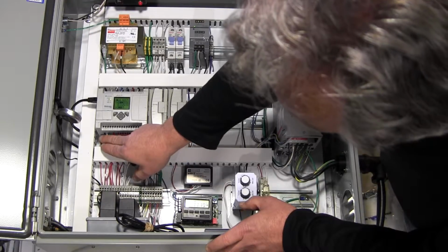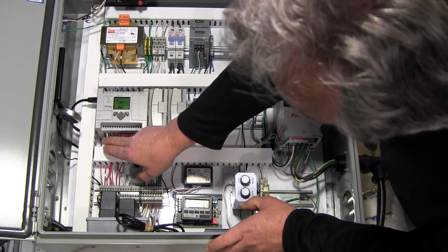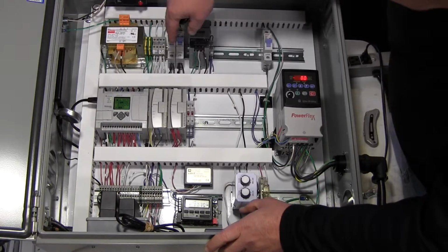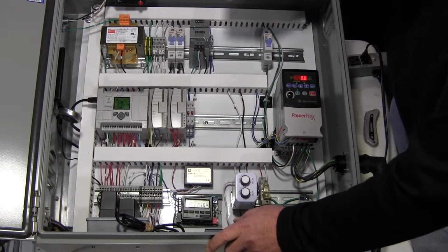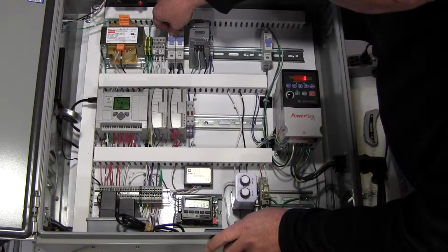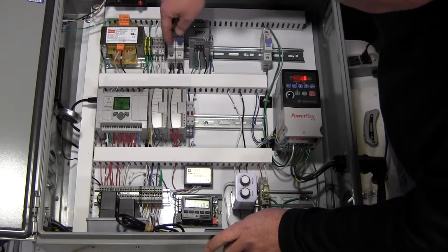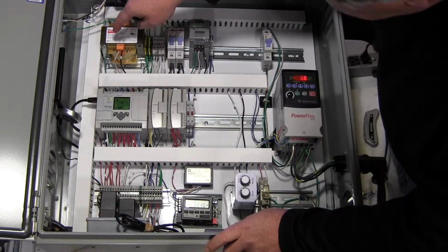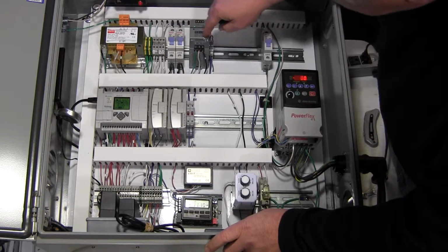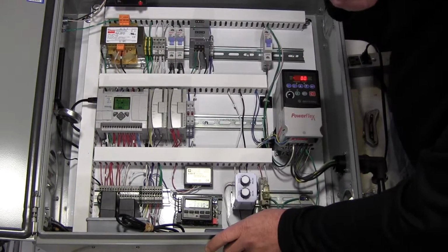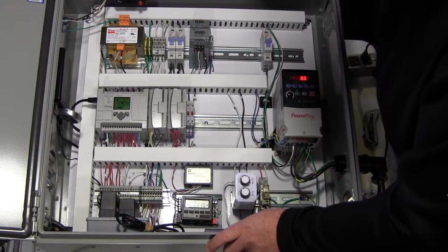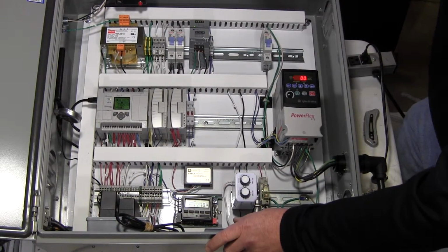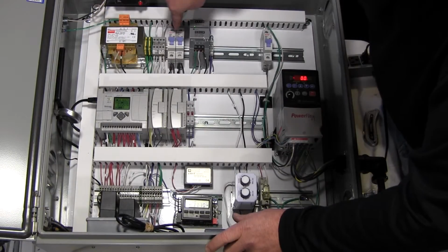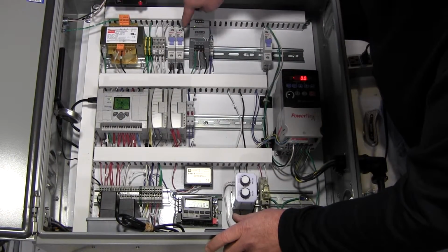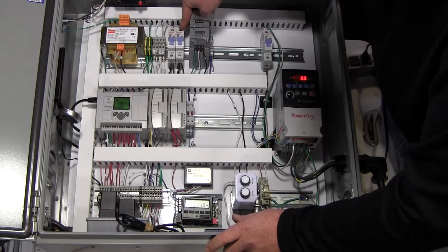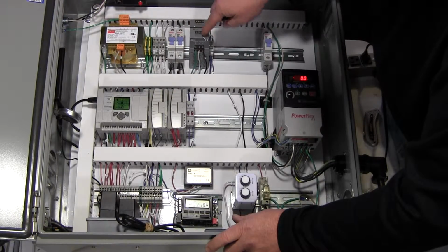Right here there's a black wire and a white wire and a green wire. That black wire and white wire go back to these points right here. So if you take a look at the output of these circuit breakers, that's where they go. This load side, one of them goes to this transformer, one of them goes to this DC power supply, and one of them goes to this MicroLogix controller. And that's not exactly how they go. Actually, one of these wires on the output of the 10 amps, the main one, comes back and loops around to the 2 amp one for the DC power supply.